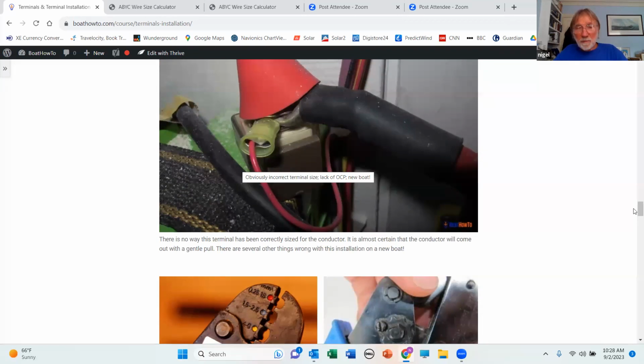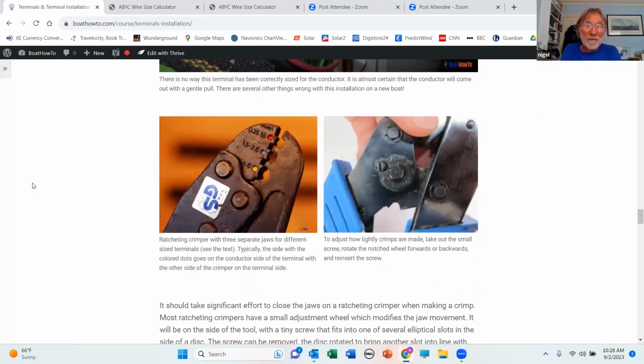So what we need is a ratcheting crimper. And they look like this. And most of them have 3 different sizes on them. One is for 18 to 20 gauge conductors, very small conductors, 16 to 14, and 10 to 12. So for 3 different conductor sizes. Typically these have 2 elliptical dies in them. The better quality ones, the dies are a different shape. The die that goes on the end of the terminal, close to where the conductor's sticking out, is more aggressive than the one that goes on the insulated barrel. So a lot of the cheaper ones, they're both the same size. So in which case it doesn't matter which way around you put the tool on the terminal. But with the better quality ones, typically speaking, the dotted side goes on the conductor side that is running away from the terminal, and the other side goes on the terminal side.